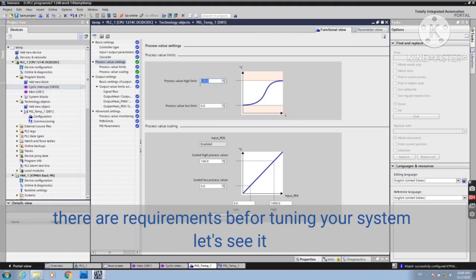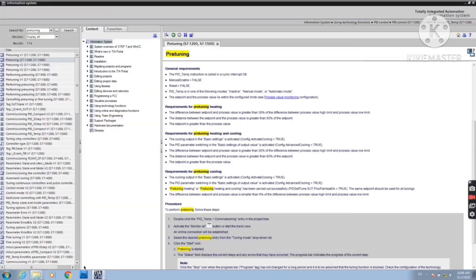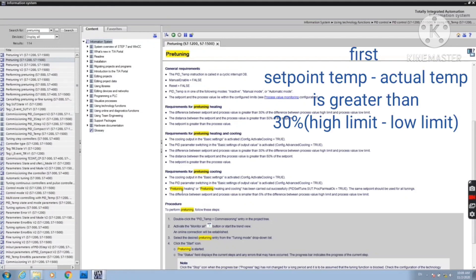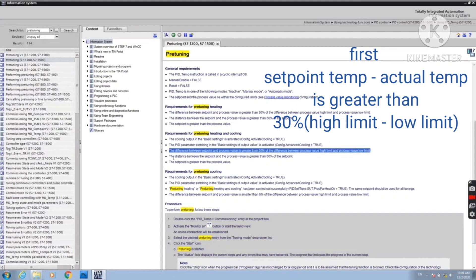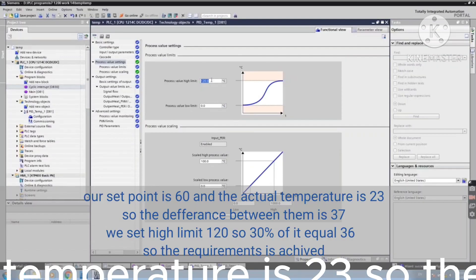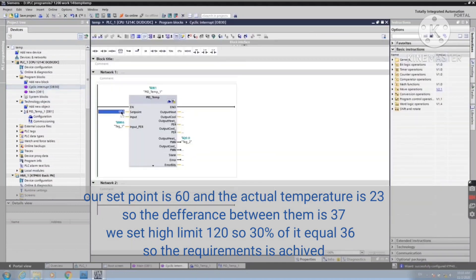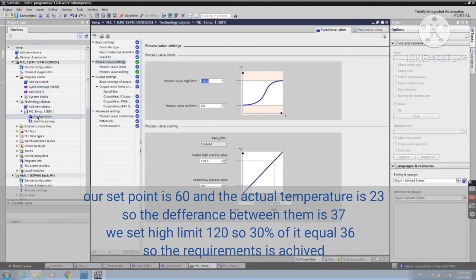There are requirements before tuning your system. First, setpoint temperature minus actual temperature must be greater than 30% of (high limit minus low limit). Our setpoint is 60 and the actual temperature is 23, so the difference between them is 37. We set the high limit to 120, so 30% of it equals 36, so the requirement is achieved.